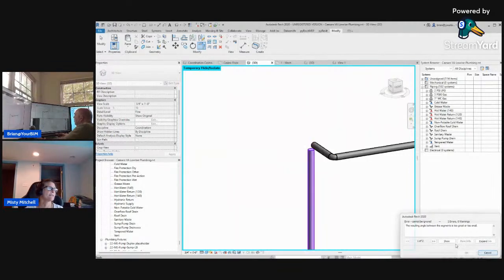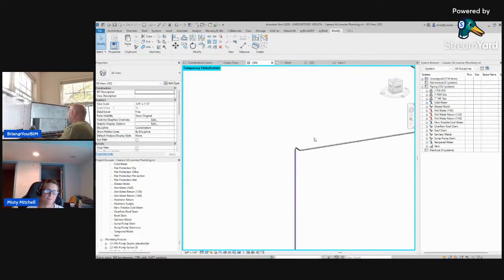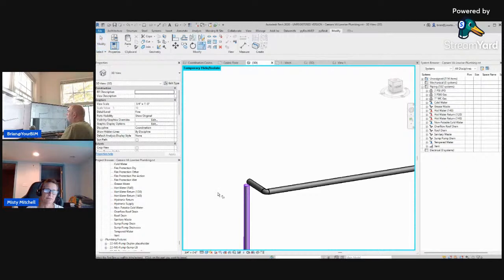It seems like he just got started off on a really bad pipe type, and we should be able to draw this whole thing now with the new pipe system that we made. Let's try that. I think what ended up happening is this guy is a 1/4 inch slope. So let me ask you a question. If I change this to a 1/8 inch slope, I think that'll fix it. Will that fix it? It will.